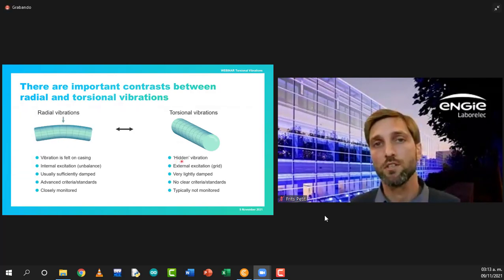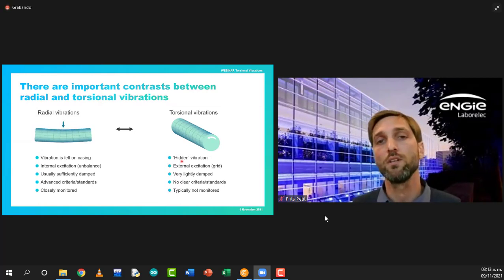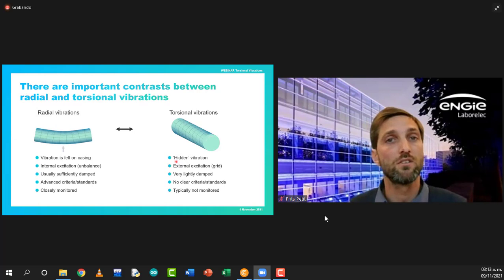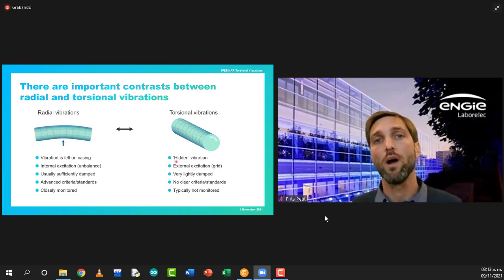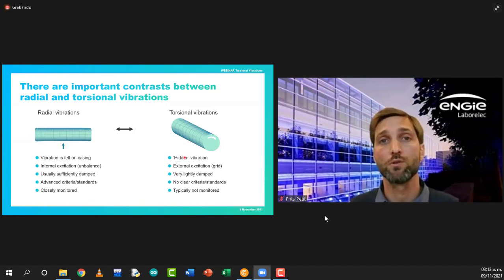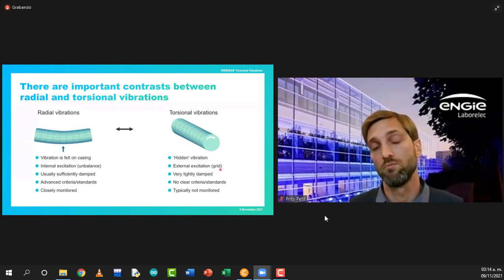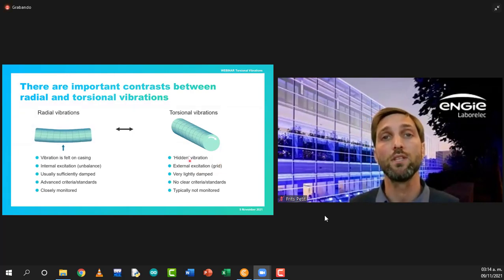The forces are not transferred to the stator casing and to the surroundings. So you could be standing in a machine room and thinking, oh, my machine is running smoothly, while in reality, excessive torsional vibrations could be present. Typically, the excitation is external, mainly due to an interaction with the grid.